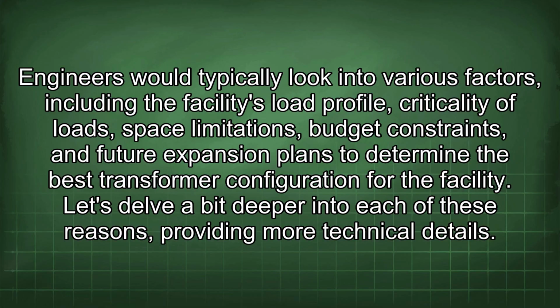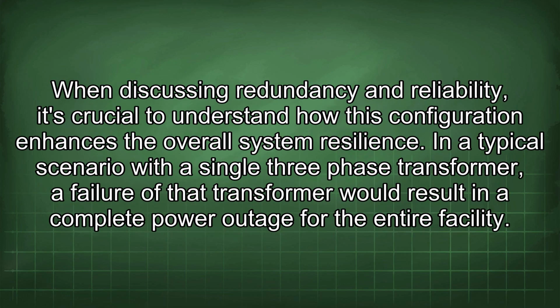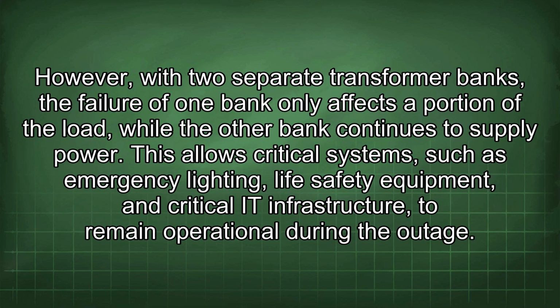Let's delve a bit deeper into each of these reasons, providing more technical details. When discussing redundancy and reliability, it's crucial to understand how this configuration enhances the overall system resilience. In a typical scenario with a single three-phase transformer, a failure of that transformer would result in a complete power outage for the entire facility. However, with two separate transformer banks, the failure of one bank only affects a portion of the load, while the other bank continues to supply power. This allows critical systems, such as emergency lighting, life safety equipment, and critical IT infrastructure, to remain operational during the outage.